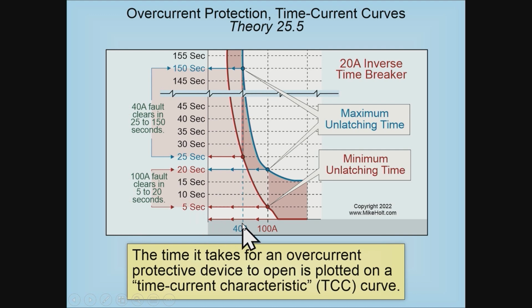So now, here is a 20 amp breaker. If I took 20 amps, and maybe we can put 20 amps here, and I go up, it should just miss this red line here, which means that time-wise, you should be able to put 20 amps on a 20 amp breaker continuously. Definitely. Now, if we go to 40 amps, you go up.